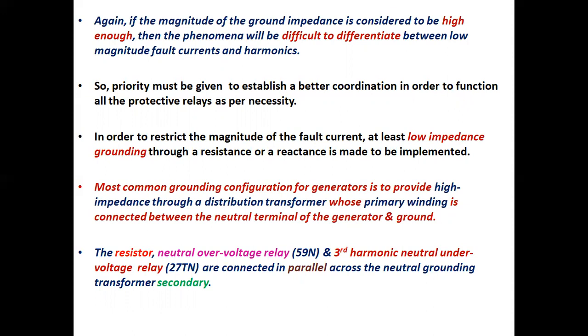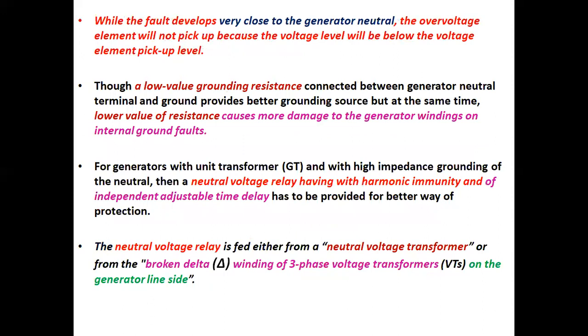The most common grounding configuration for generators is to provide high impedance through a distribution transformer whose primary winding is connected between the neutral terminal of the generator and ground. The resistor, neutral overvoltage relay 59N, and third harmonic neutral undervoltage relay 27TN are connected in parallel across the neutral grounding transformer secondary. While the fault develops very close to the generator neutral, the overvoltage element will not pick up because the voltage level will be below the voltage element pickup level.